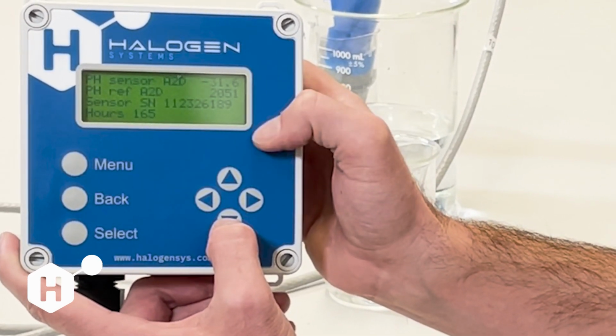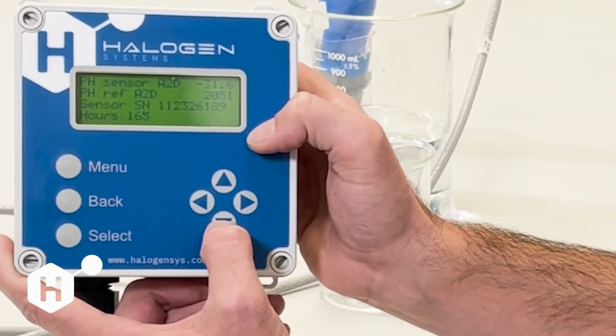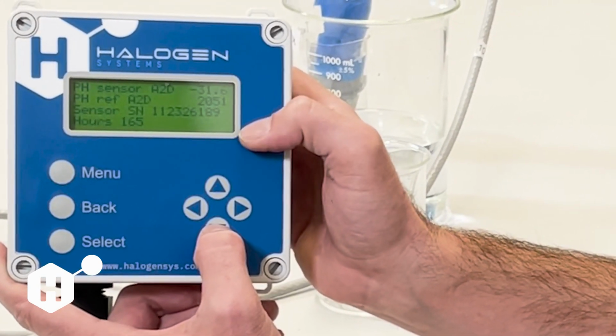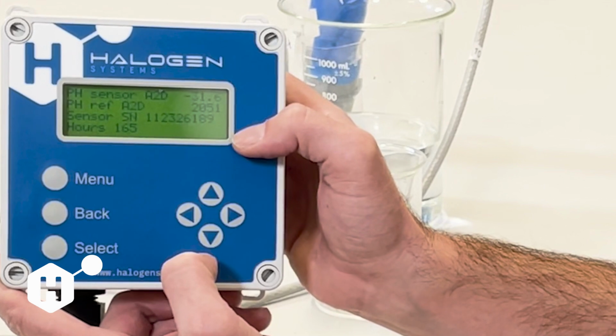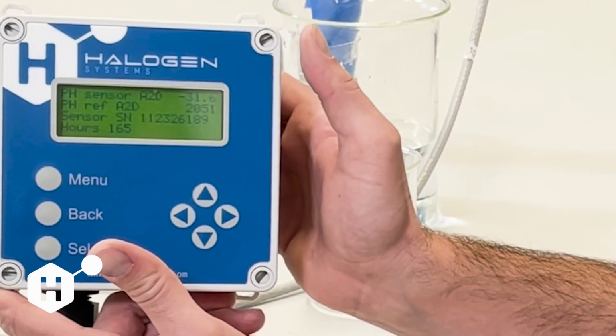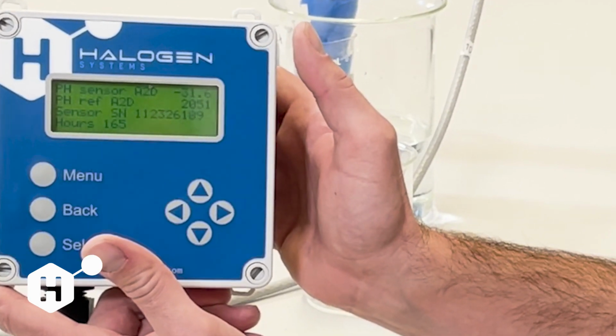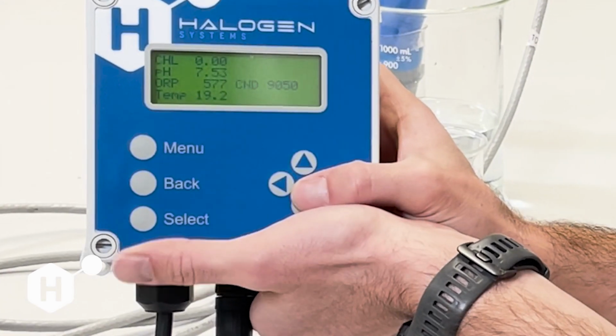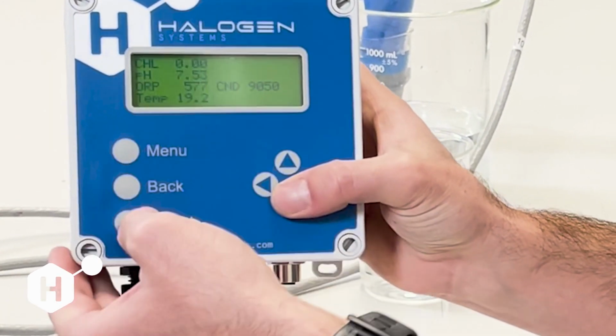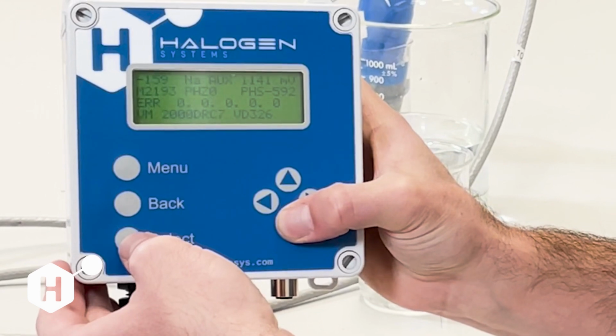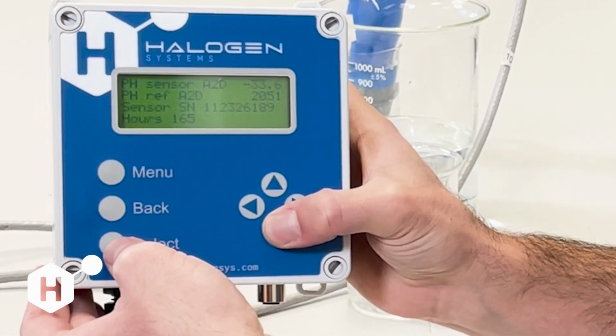So we're going to open back up, negative 31.6. And I'm going to wait until I see that value change again, or if it changed. If it doesn't change across 2 to 3 minutes, then we know that we're pretty stable. As you can see, our pH is starting to drop. We'll go ahead and take a look and see what our millivolt value is, negative 33.6.